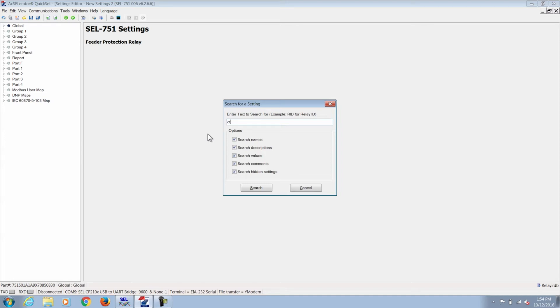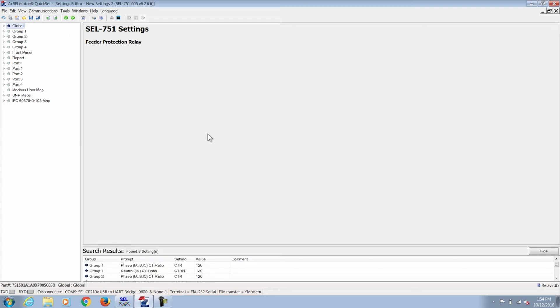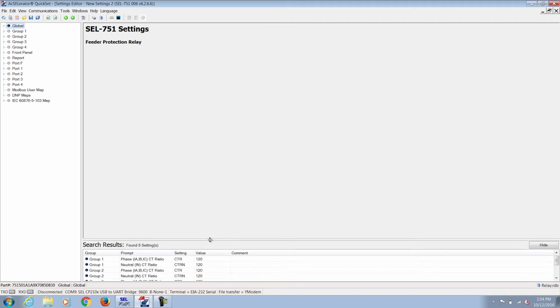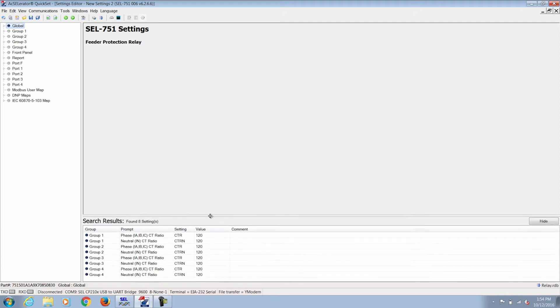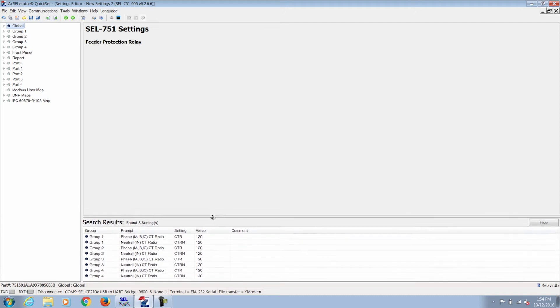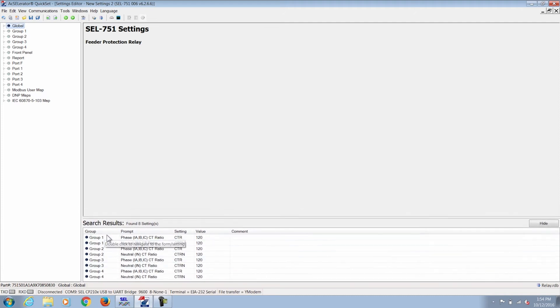So here for example I'm typing in the CTR setting for the current transformer ratio. On the bottom it gives me the search results and you can see it's for all of the multiple groups. We only need to go into the group one because this is the active group.